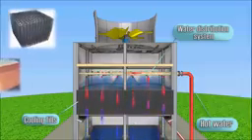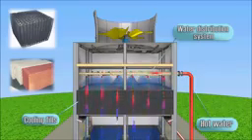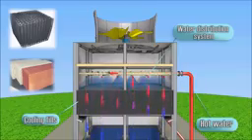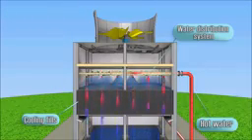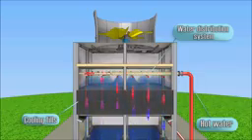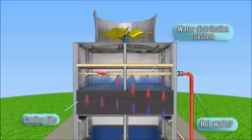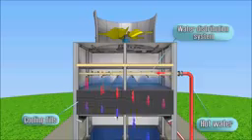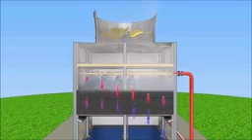On the fills the water film is formed, from the surface of which the water evaporates and encounters the airflow. The larger the surface area of the fills, the more intensive is the evaporation of water, and the more efficient is the cooling tower. Evaporation is accompanied by expenditure of energy required to convert liquid to vapor. Humidity of the air increases when water evaporates.